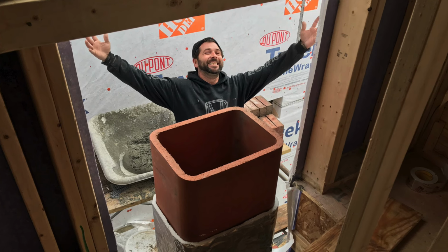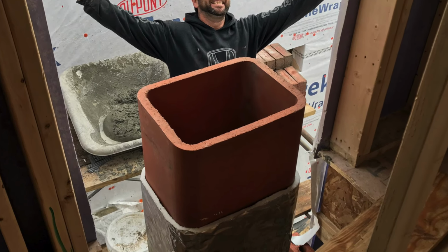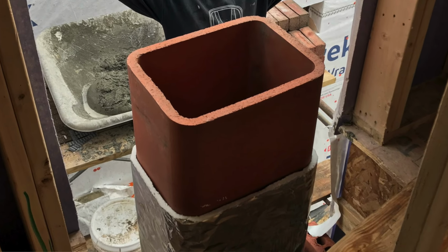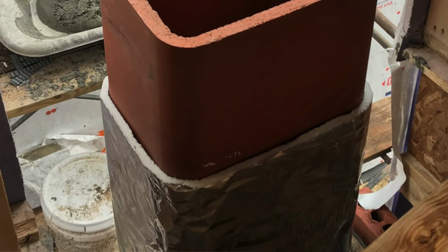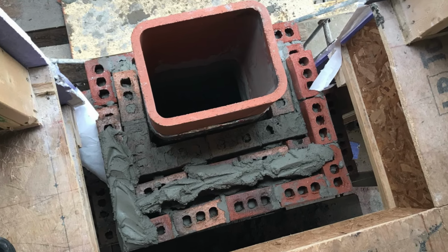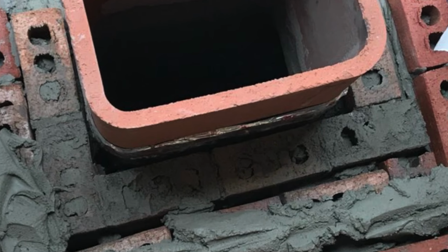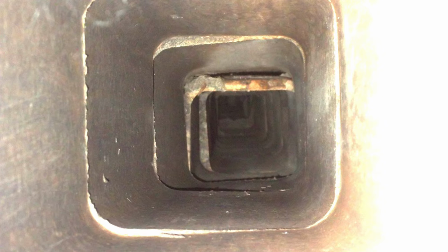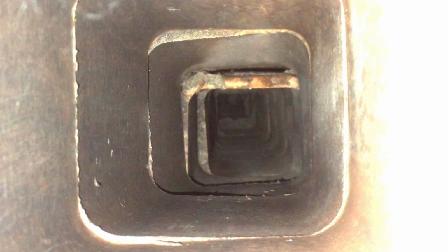One of the most important requirements is that the liner must not be bonded to the surrounding chimney structure. Clay flue tiles expand when heated, and the chimney walls do not expand at the same rate. For this reason, the liner must be free to move independently with thermal expansion. The separation space should be no more than the thickness of the liner wall, typically 5/8 inch for standard flue tiles. Excessive spacing creates structural weakness, while a bonded liner creates stress that inevitably leads to cracking, crushing of mortar joints, or buckling of the flue during thermal cycles.